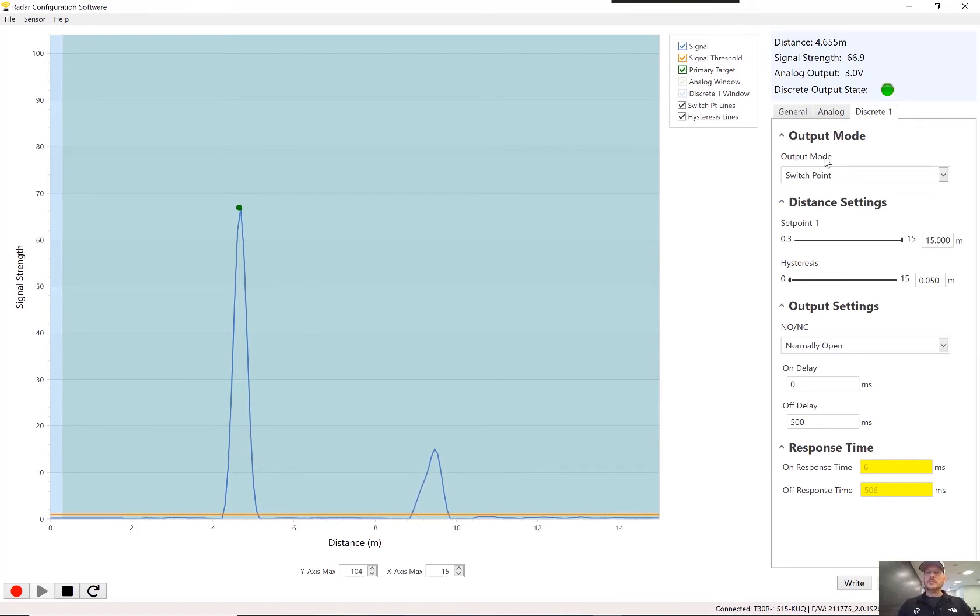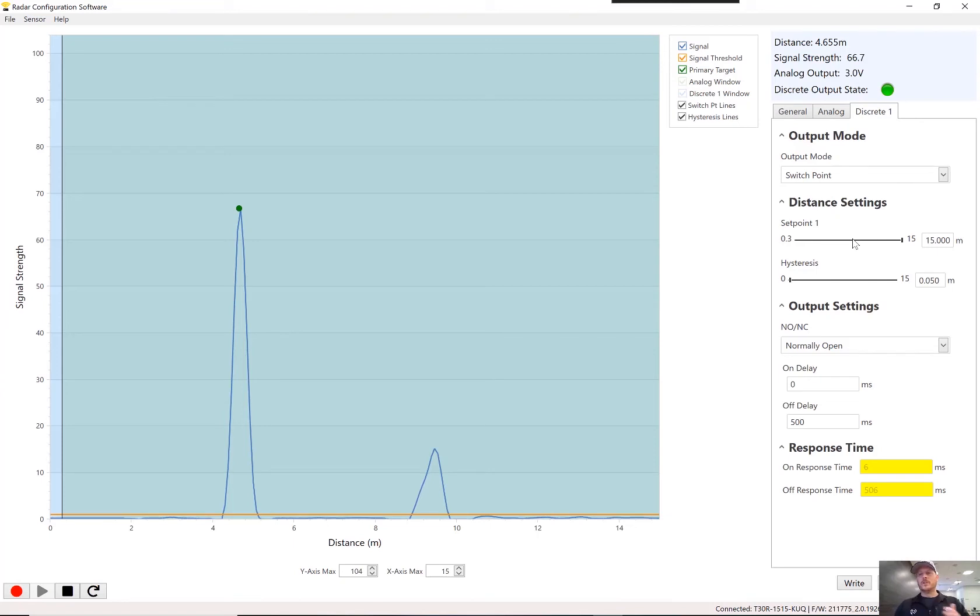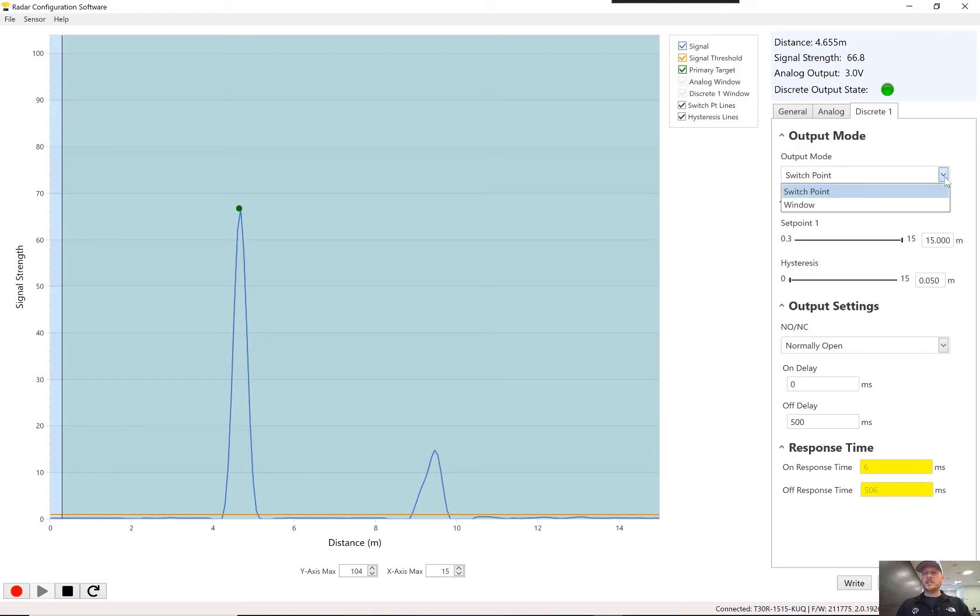Let's go over to the discrete output or the switch point. And there are a couple of different modes here. The switch point is you can set it so that the output will turn on or turn off when the target is at a specific distance and then further or closer, depending on how you have your normally open, normally closed settings. However, another nice feature is this window type mode.